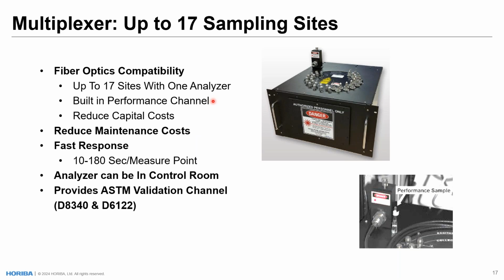Technically, the multiplexer is interfaced with 18 channels, but we do reserve the very first one for a built-in performance channel. The built-in performance channel ensures that the system is reliably accurate over time by using a performance sample, typically toluene, to diagnose and monitor key indicators of your analyzer's performance and health. If something is wrong with the performance sample, or if the performance sample spectra being collected is not what is expected, our software, our analyzer, will recognize that and flash a preventative warning to you regarding the analyzer, which also helps reduce maintenance cost overall. And this also provides ASTM validation channel procedure checks, we can say, with this built-in performance channel.